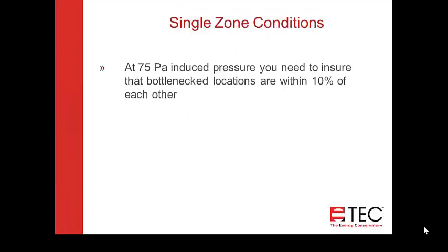We need to set the building up in single zone conditions typically. In commercial building testing we can get into more complicated configurations. Ideally you want to test in single zone conditions, and typically commercial buildings are tested at 75 pascals instead of 50. That's pretty widespread — it is the new standard for testing larger commercial buildings. To set up single zone conditions, you'll want to make sure bottleneck locations are within 10% of each other, measuring interior pressures to ensure there's not more than a 10% spread between far reaches or bottlenecked areas of the building.